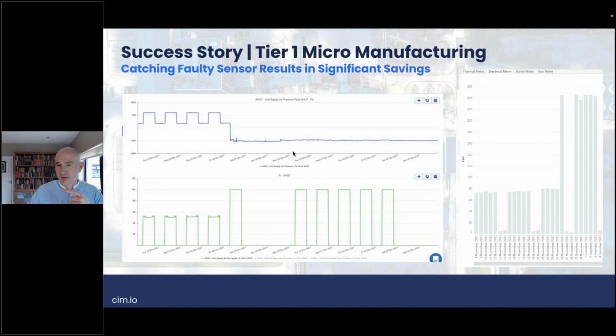So the software in this instance identified that the static air pressure sensor had gone faulty and needed to be changed, and it was about 200 euros to fix that. As a result of that instrument being changed in the field, you now have a 37 kilowatt supply fan that is now running at maybe 10 kilowatts because it's able to back off from that 50%. On the right here it shows the energy consumption before versus after, so it's a significant win around the instrumentation. That was a key point we've noticed.